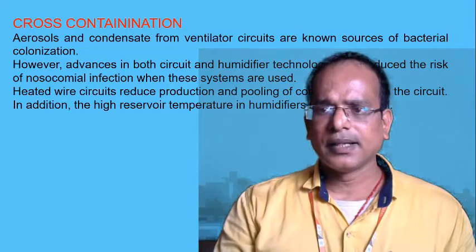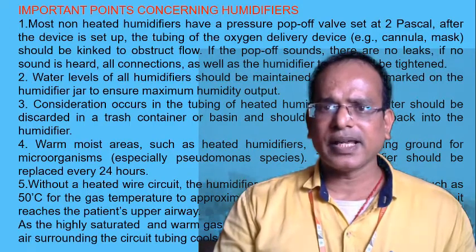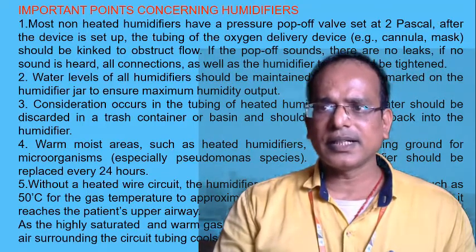The important points to consider with a humidifier: most non-heated humidifiers have a pressure pop-off valve set at 2 Pascal. After the device is set up, the tubing of the oxygen delivery device, for example a cannula or a mouth mask, should be pinched to obstruct the flow.